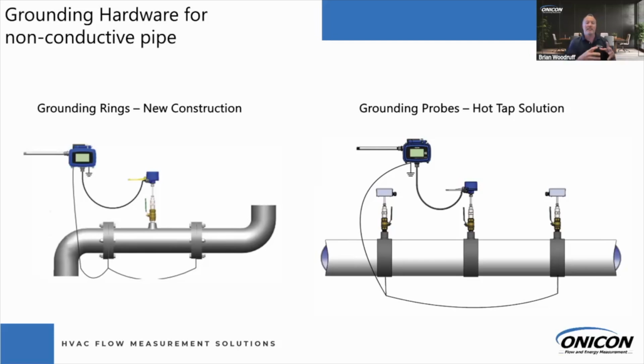Well, the thing about this technology and considering the electromagnetic is you're going to have grounding rings and/or grounding probes installed in that pipe. So new construction, it's great because you have to actually flange in the grounding ring. But if it's going to be a retrofit, you can do our grounding probes.